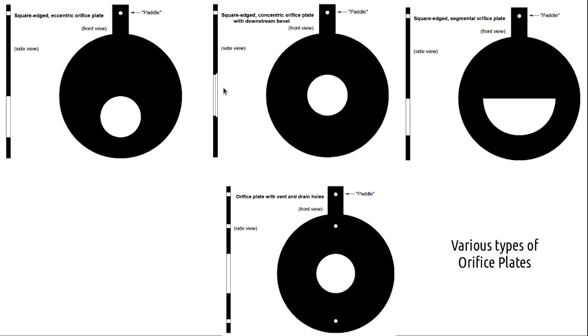From the side view you see that even though the top view shows a circular section, it in fact has a variable diameter. So the orientation will be mentioned, which is the upstream side and downstream side, clearly written on this paddle. If you put it the other way around, that's not the right way to do it.